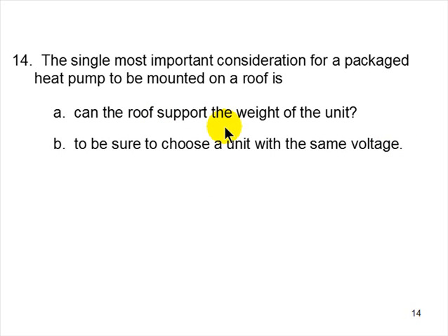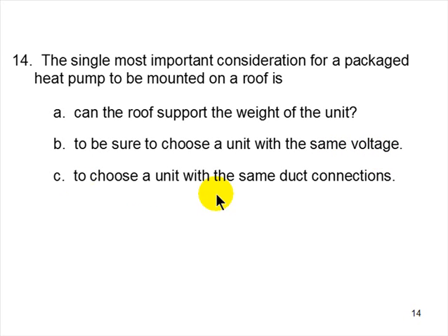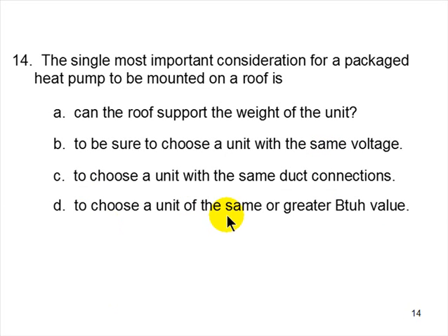To be sure that you choose a unit with the same voltage? To be sure that you choose a unit with the same duct connections as the old system that was there? To choose a unit of the same or greater BTU value. If you're replacing a unit on a roof, don't assume that because it's the same size and same voltage, it has the same weight. Okay? And that, in fact, the roof can support that weight.